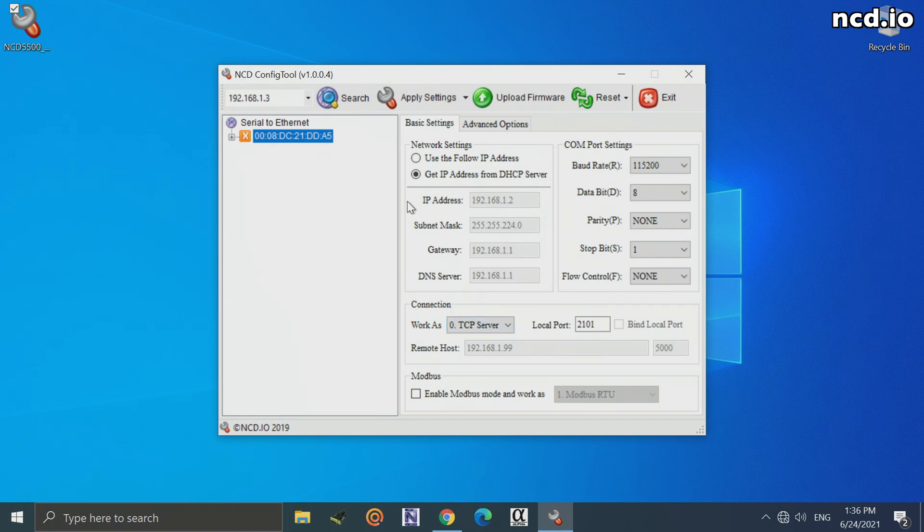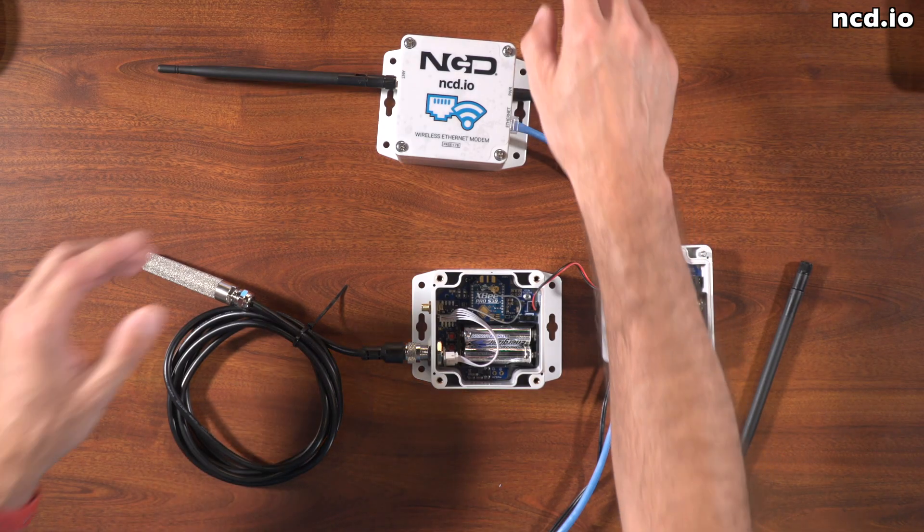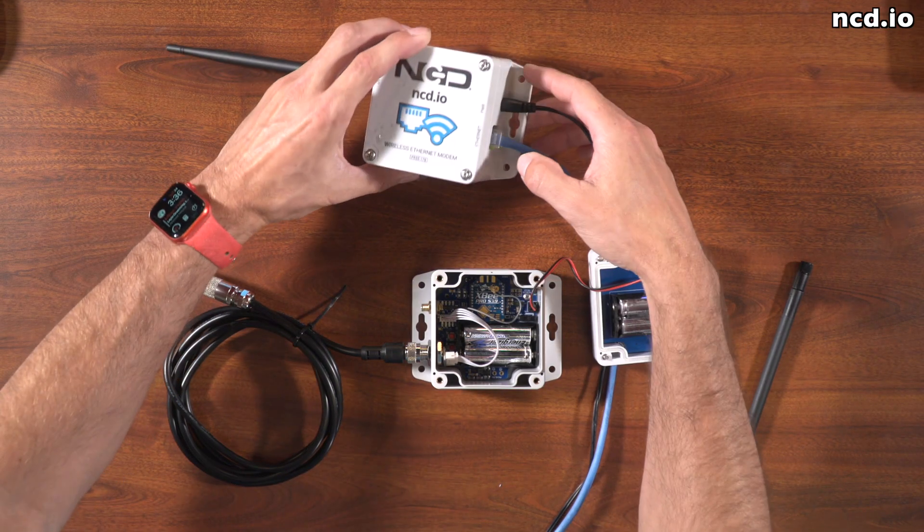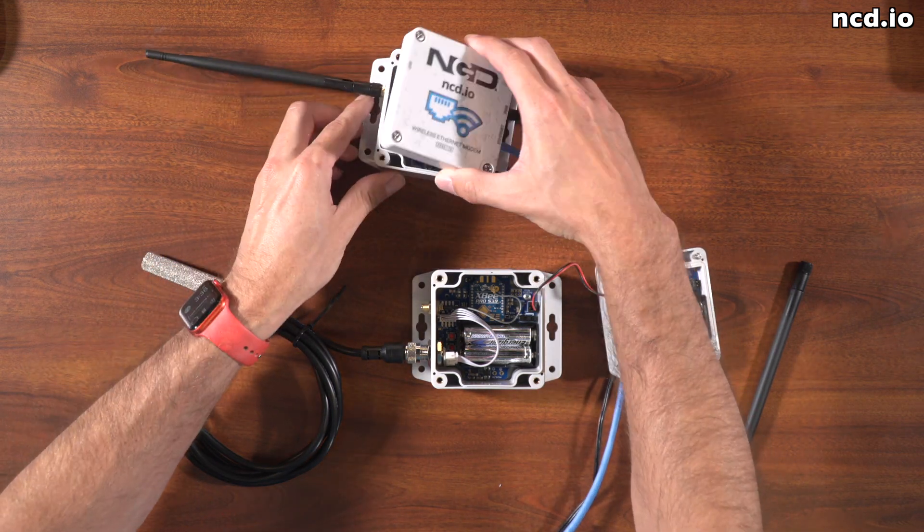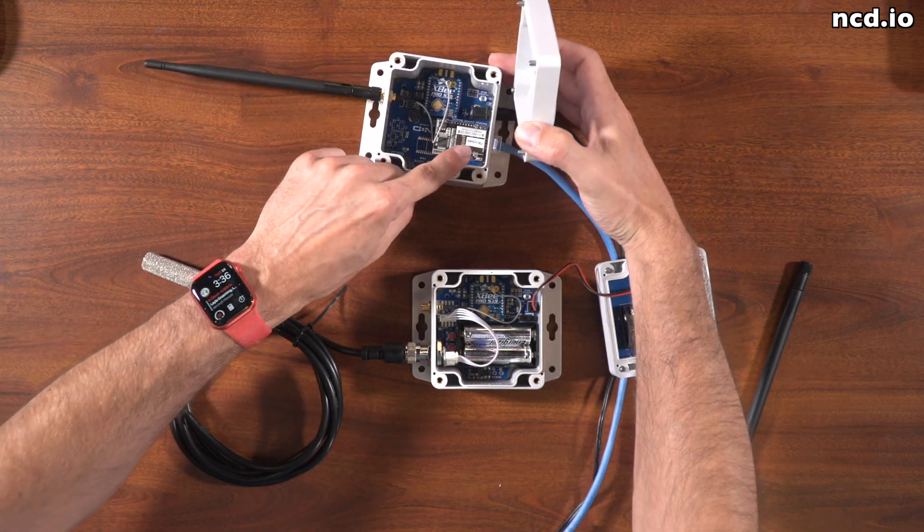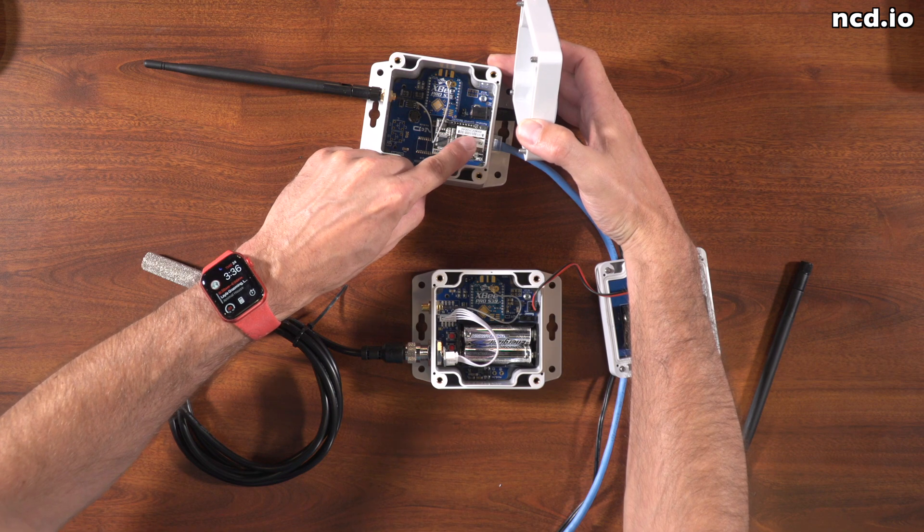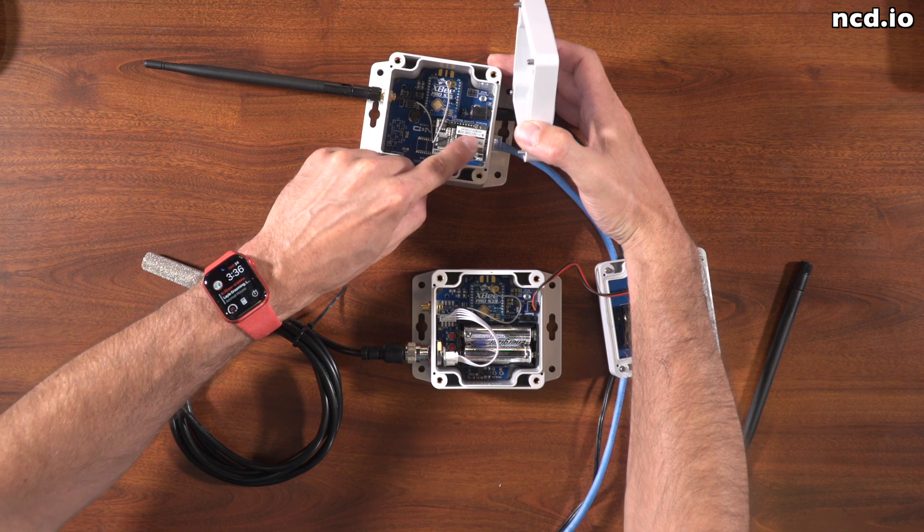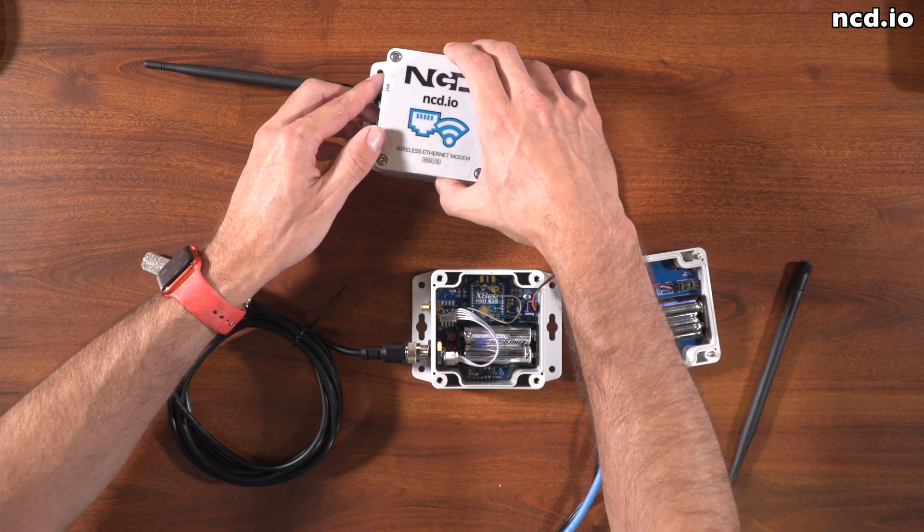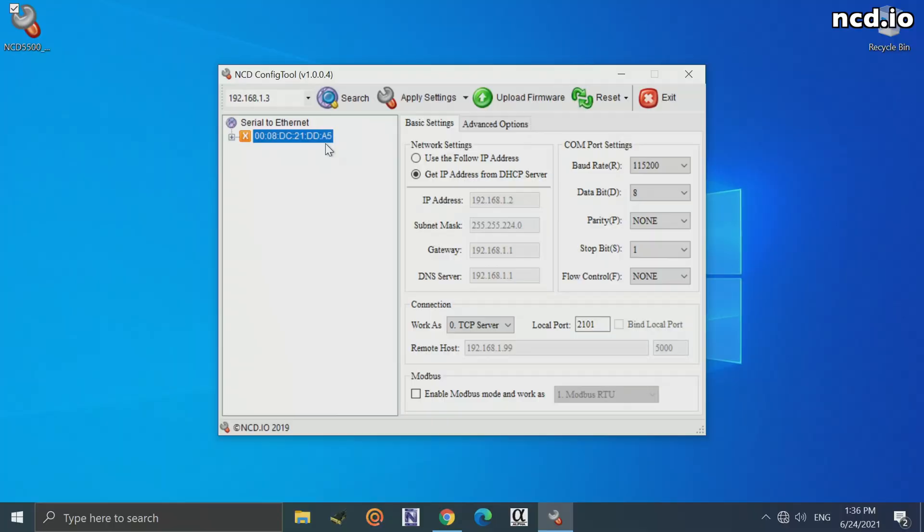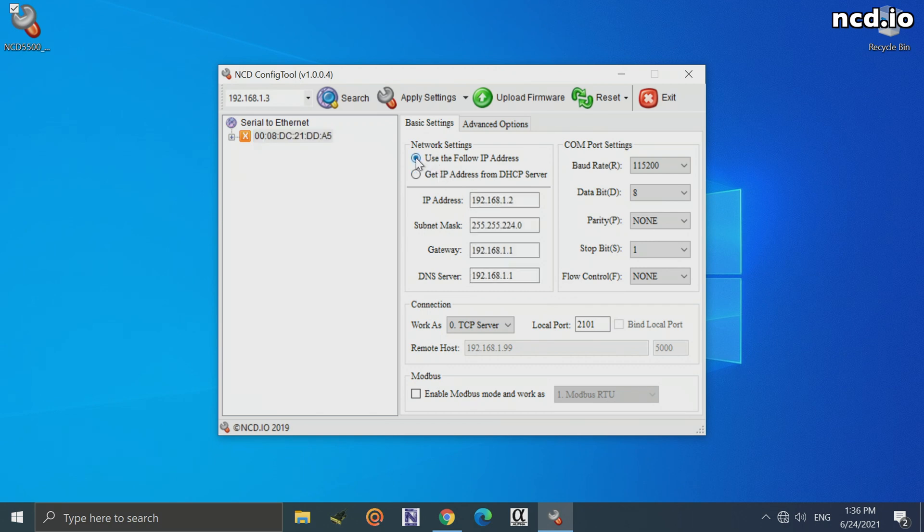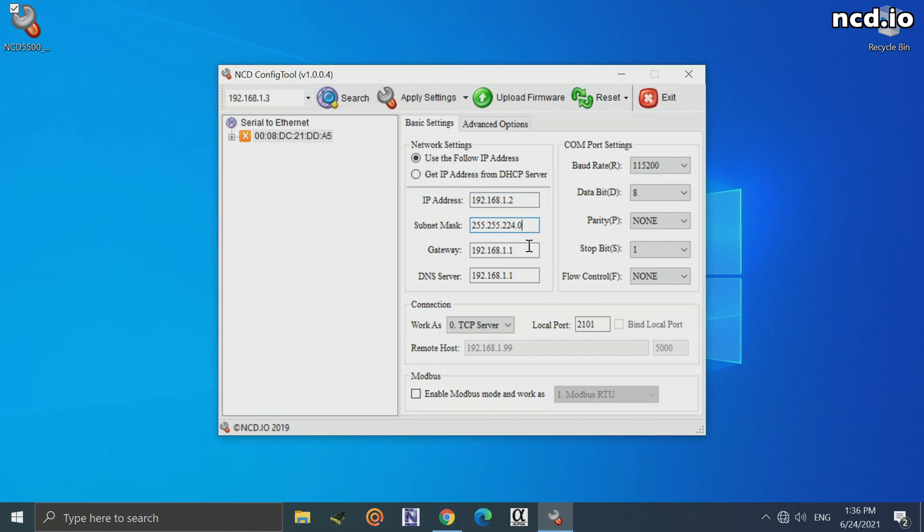After we open the software up, we'll see it actually already discovered our device right here. We can see its MAC address. You can also find the MAC address of your modem by opening the box and reading the MAC address printed right here on top of the Ethernet interface module. Here we'll see some advanced configuration settings. We can tell it to use a static IP address by switching to this option, use the following IP address. That allows us to enter an IP address, subnet mask, gateway, and DNS server. I'm going to leave it to DHCP for my purposes.